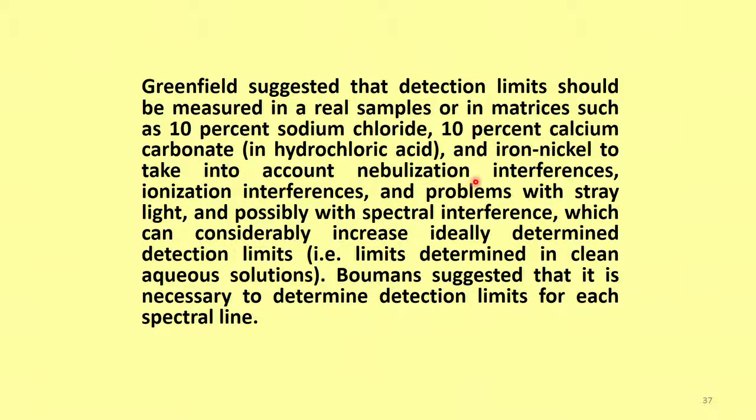Anyway, in general the sample should match the matrix of the material in which you want to analyze. This reduces the nebulization interferences, ionization interferences, and problems with stray light, possibly with spectral interference, which can considerably increase the ideally determined detection limit.